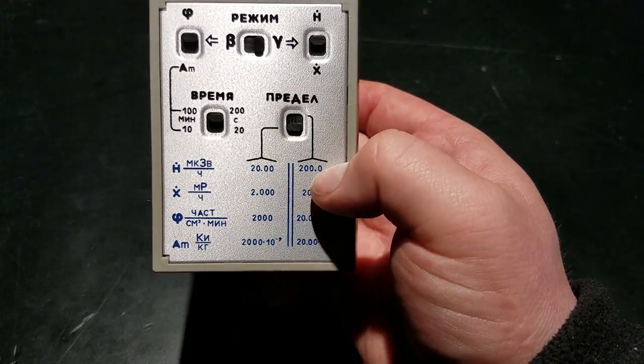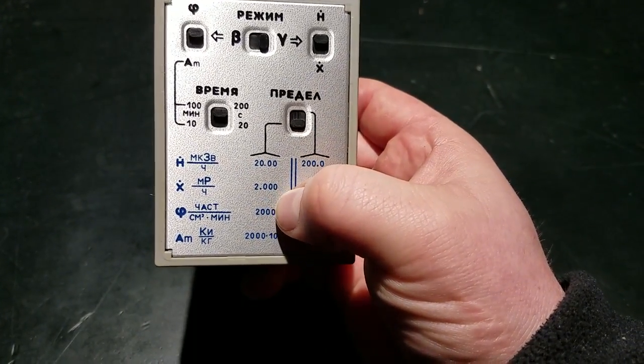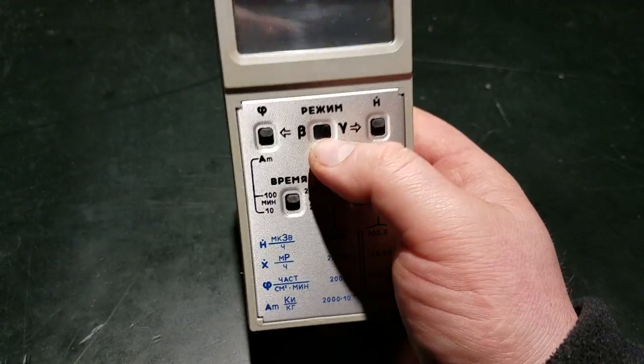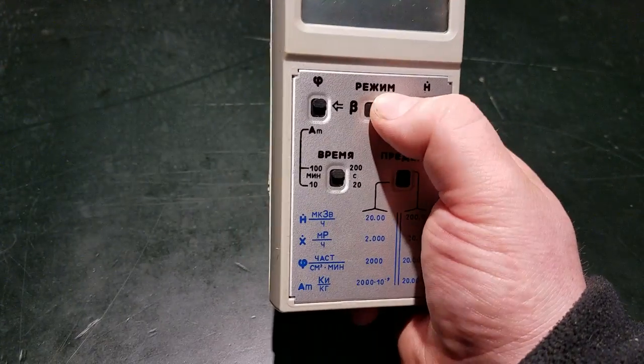There's two levels, like the max level here. You can have 20 microsieverts per hour or 200 microsieverts per hour, or 2 milliroentgens per hour or 20 milliroentgens per hour. That's in gamma mode.